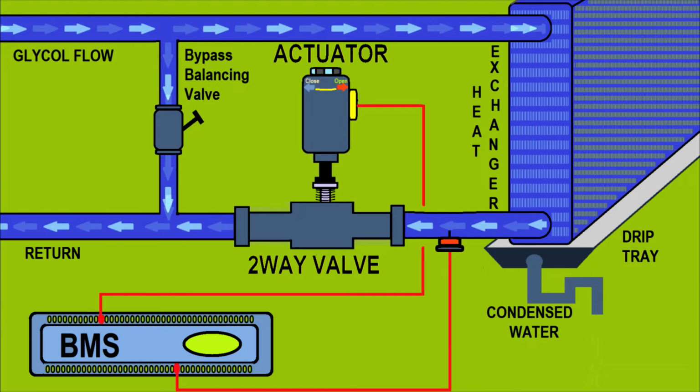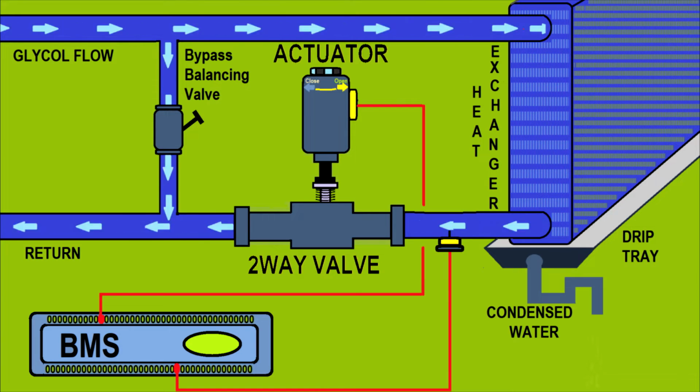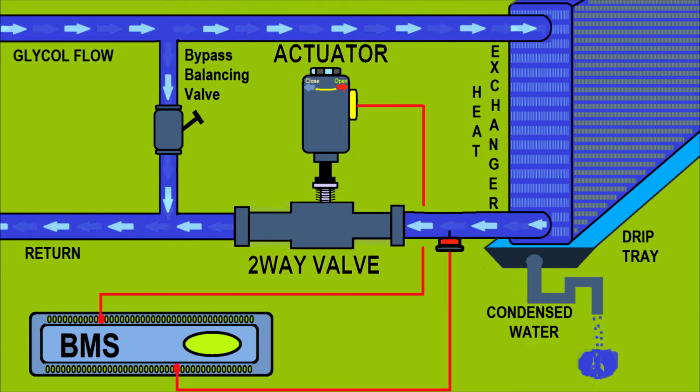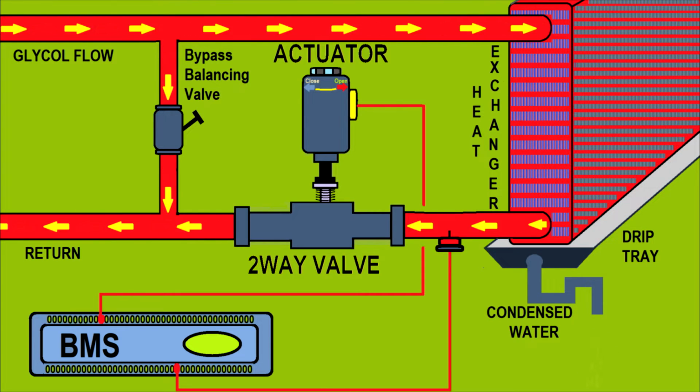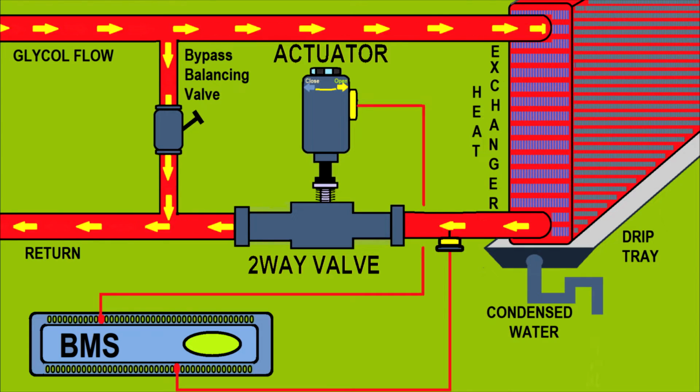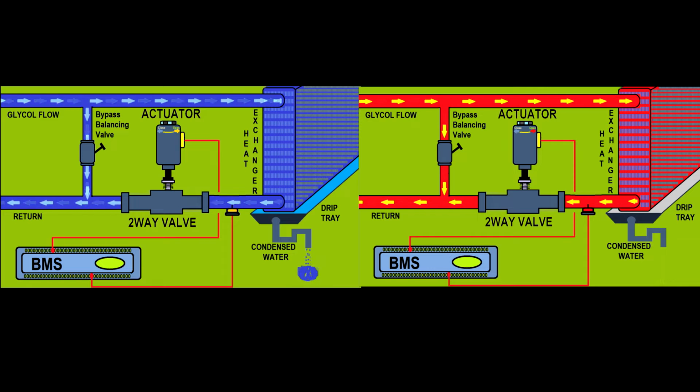To control the humidity, we use heat exchangers. Like in this case, we have a cooling agent that passes through the heat exchanger. This cooling agent is regulated by a two-way valve, which is controlled by an actuator. So even if we use heaters, coolers, or both, the cooling and heating agent will be controlled by a programmable logic control. We will instruct the valve to operate more or less according to the heating or cooling demand.